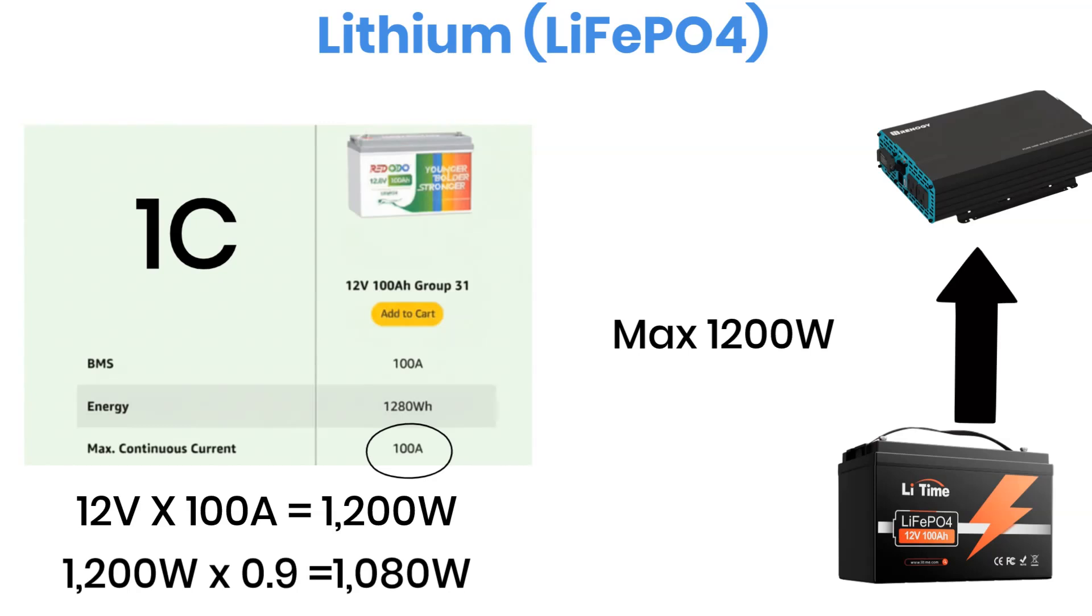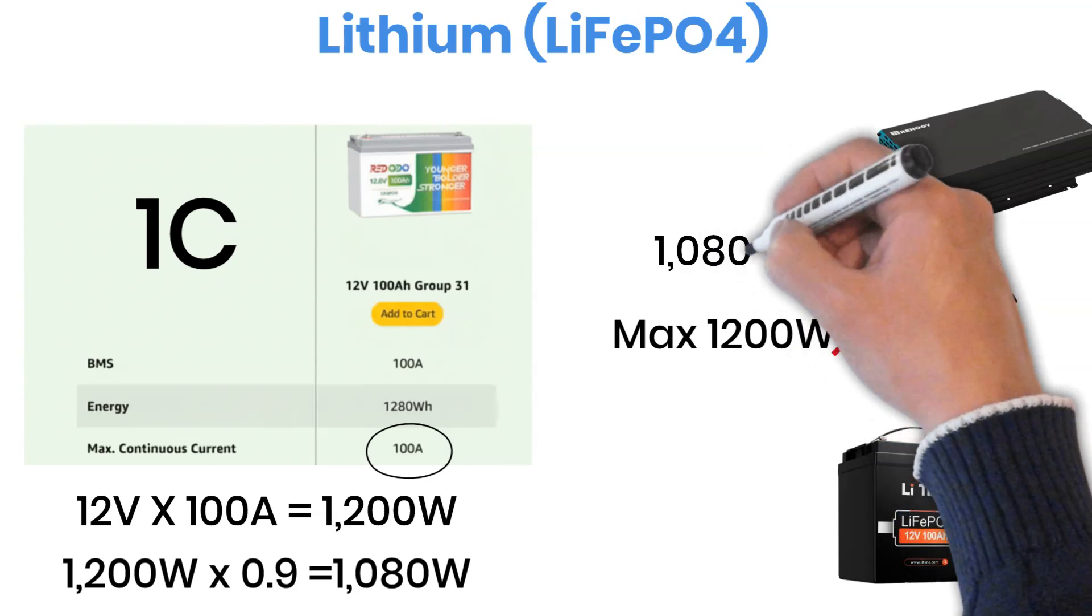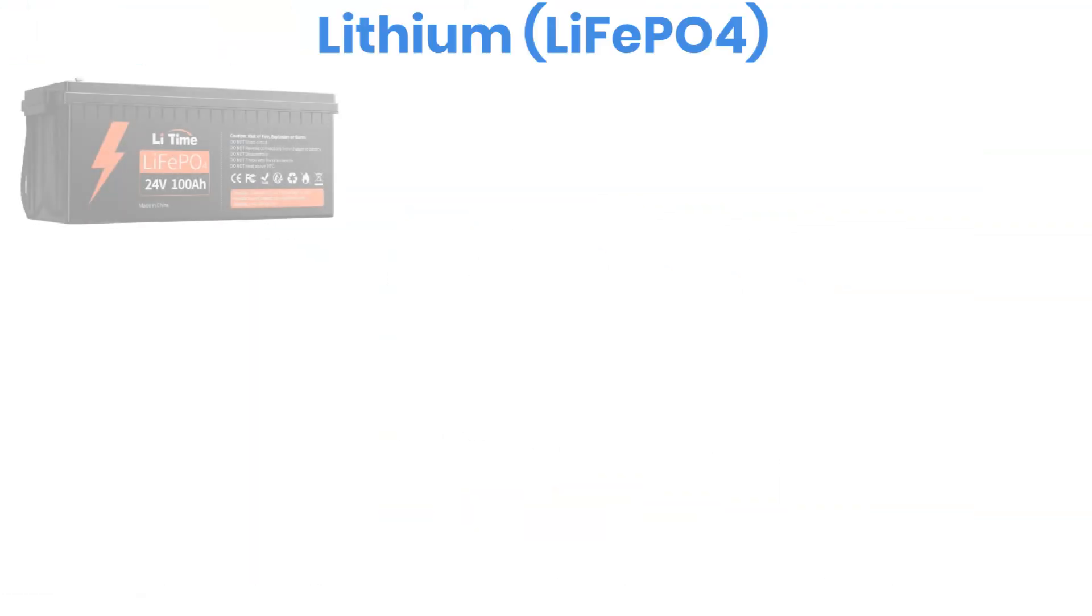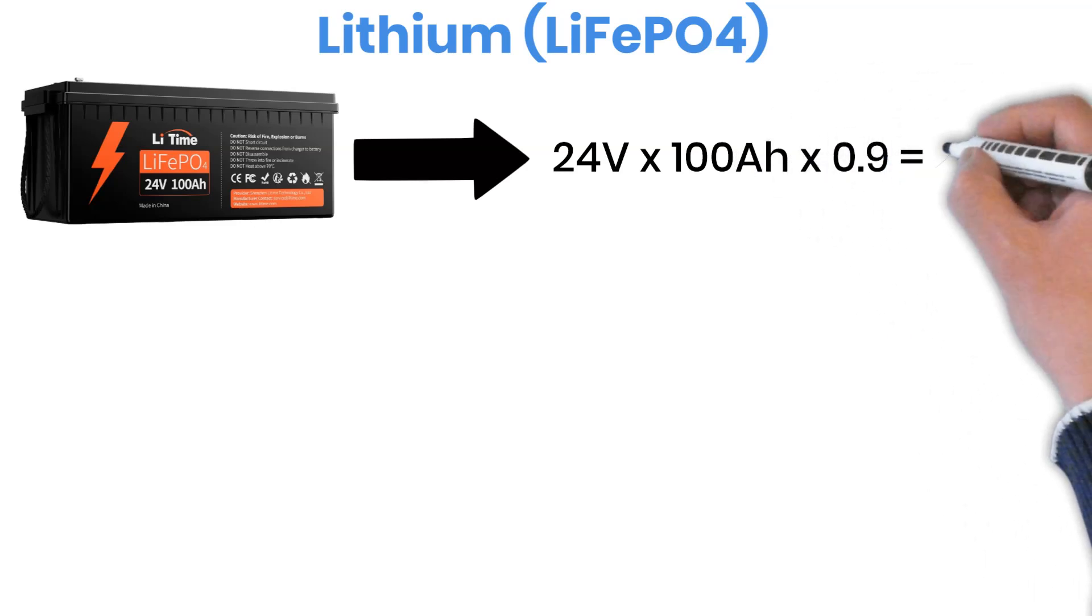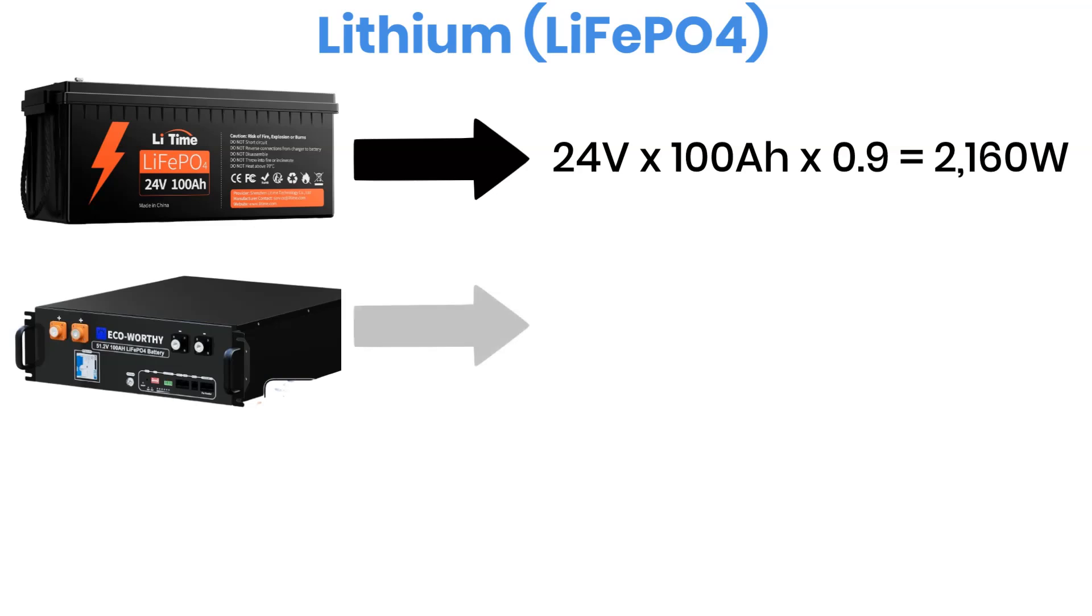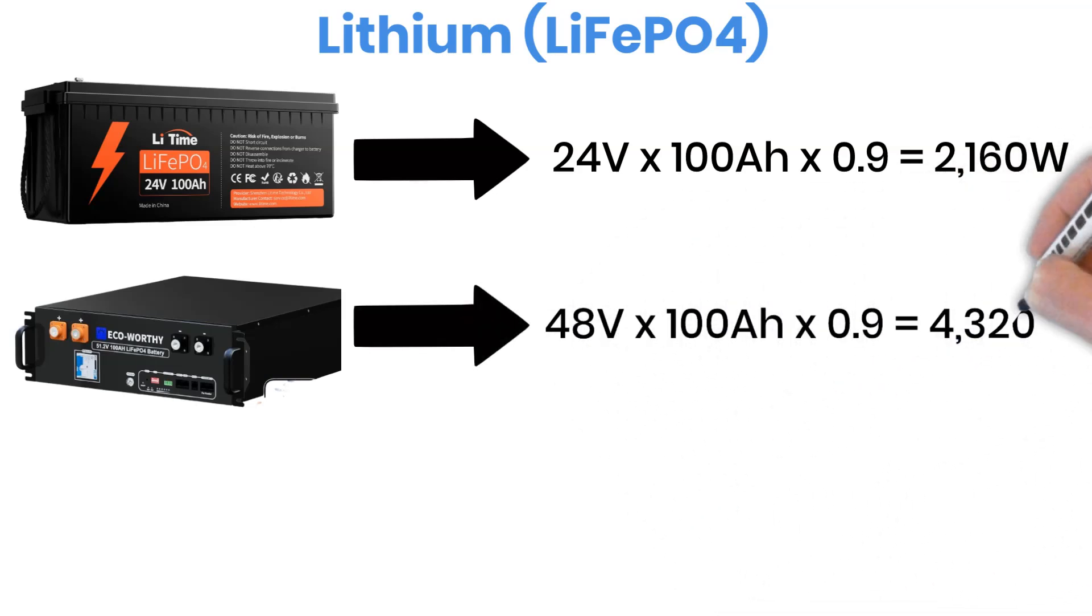That's why, for a 12 volt 100 amp hour lithium battery, the biggest inverter you should pick is roughly 1,000 watts. If you've got a 24 volt 100 amp hour lithium battery, then the limit doubles, around 2,000 watts. And for a 48 volt 100 amp hour server type battery, you can safely go up to about 4,000 watts.